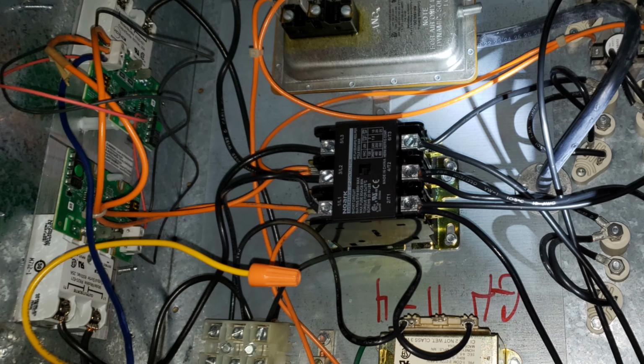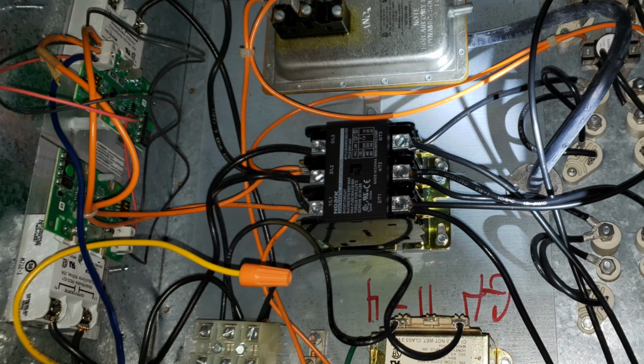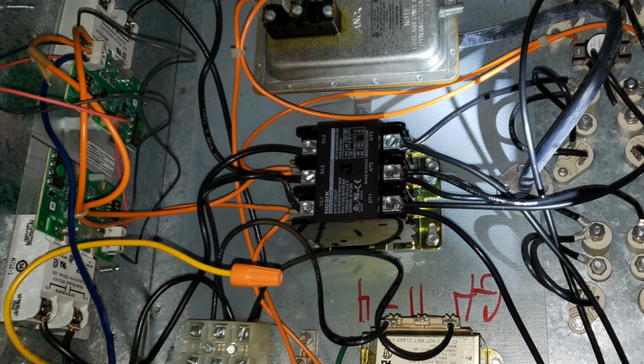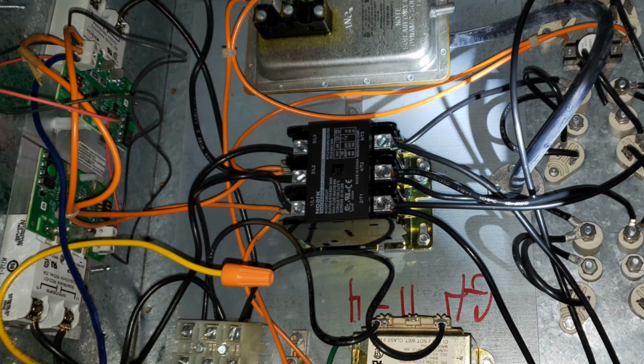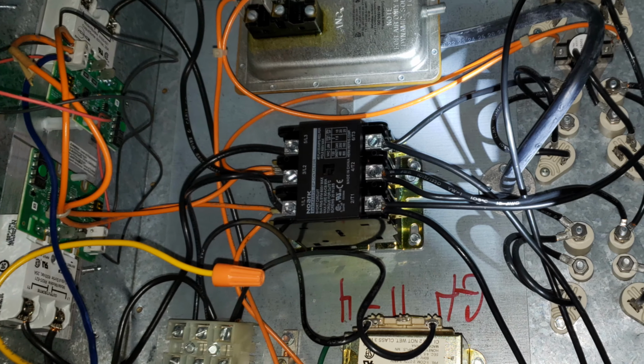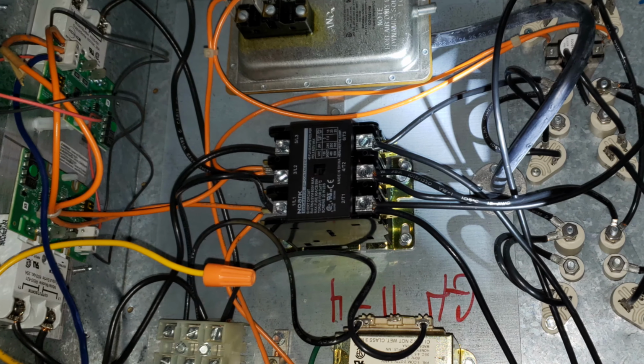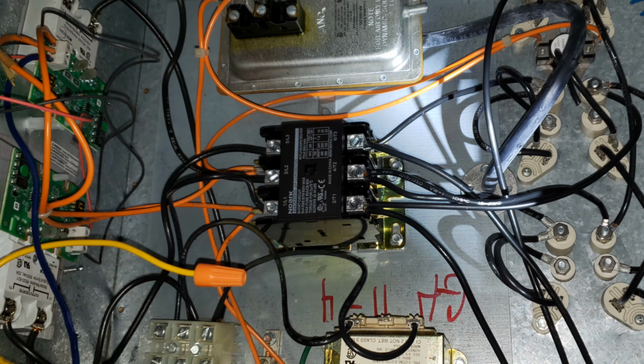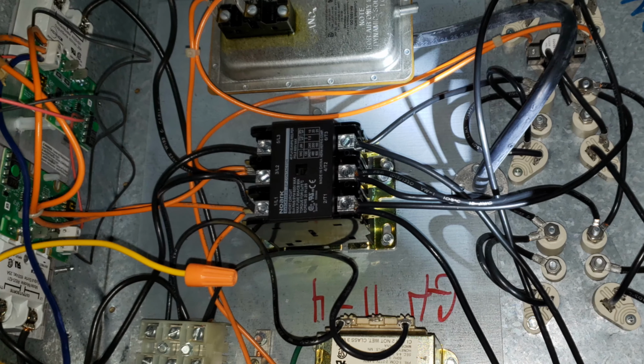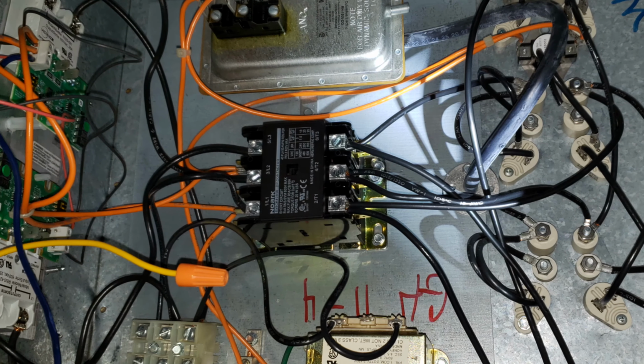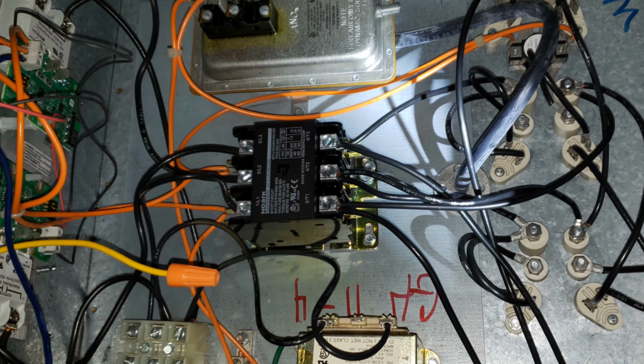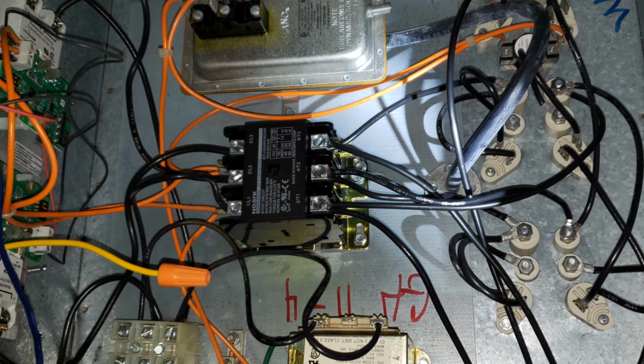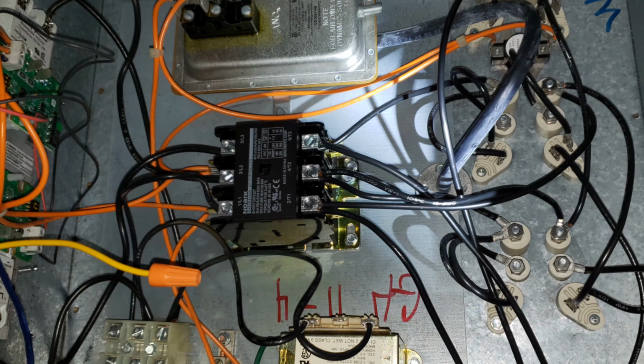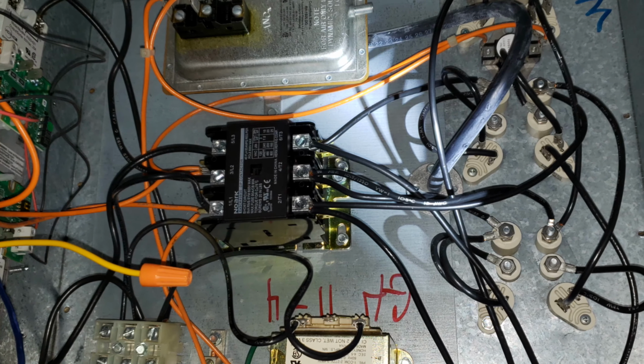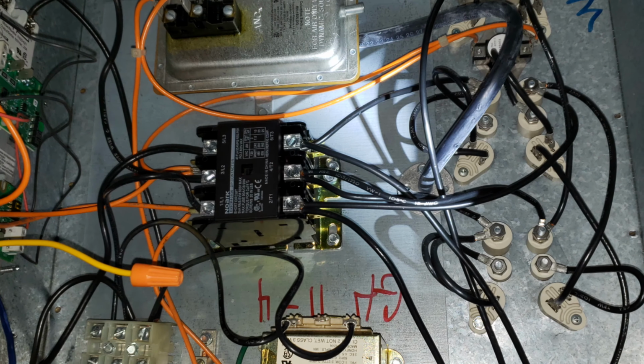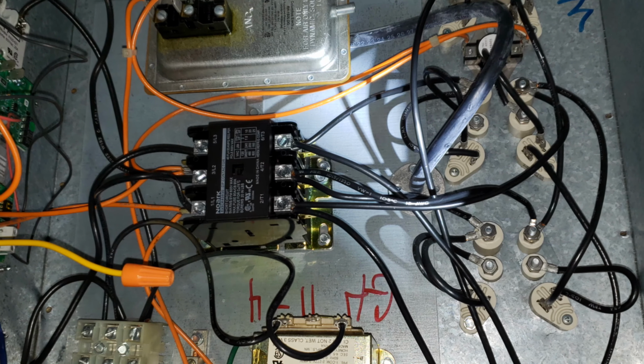This manufacturer doesn't produce a 3-phase version anymore, so with 3-phase you have to control 2 of the 3 legs of power going through the heaters. So what I had to do was purchase a second single-phase version and install them on top of each other. You can see there's 2 green boards there. That's technically 2 single-phase SCR controllers stacked. Originally there was one large 3-phase one in there that had 2 legs of control.